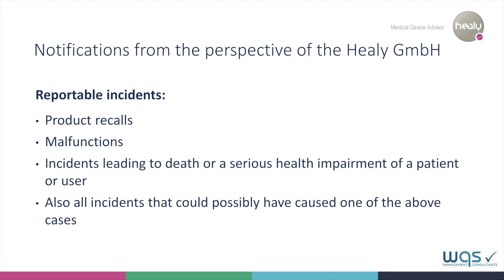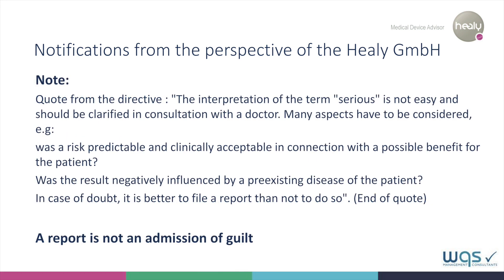As a manufacturer, we must comply with our reporting obligations in the following cases: in the event of product recalls or malfunctions attributable to product defects; in serious cases, such as a serious health impairment or even death of a user; and for all incidents that could possibly cause one of the above cases. If the term 'serious' cannot be exactly clarified by the manufacturer, the decision should be made to file a report.